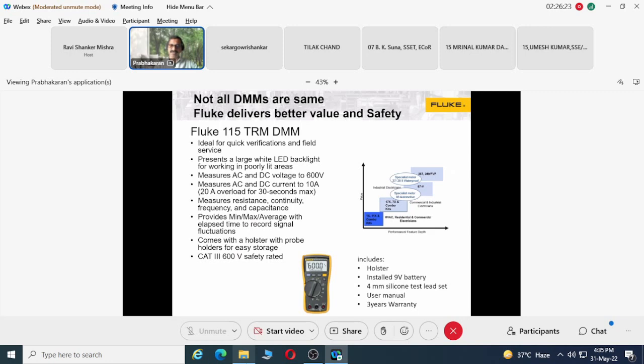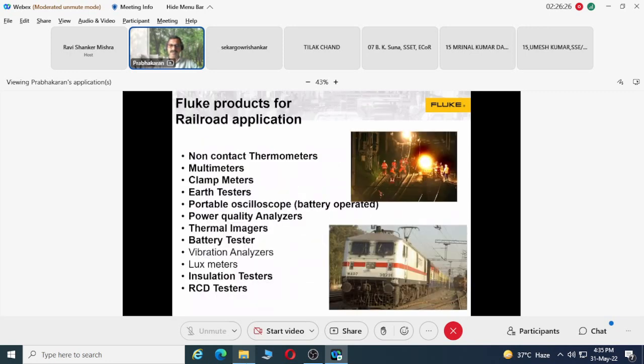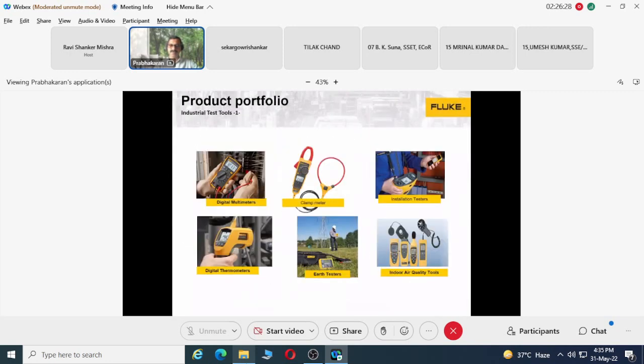This is the device—let me show it to you. This is the device which injects a leakage current into the RCD or ELCB and then gives you the timing of how fast it trips. It verifies whether it's tripping, and it also tells you the loop impedance—how much the loop impedance is and how fast it trips at what current.